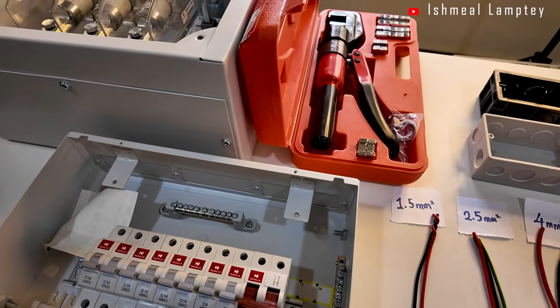But in some places you go, you have about 8, 10, 12 sockets on just one breaker. That is not correct. So it is important to sometimes question your electrician on some of these things. How many circuits are you going to have on this breaker? So that you are able to understand that, okay, whatever they are going to do is proper. The same for the lighting system. There are instances where what people do is they just loop the live cables and then the neutral cables to the various lights and fans, which is not proper.